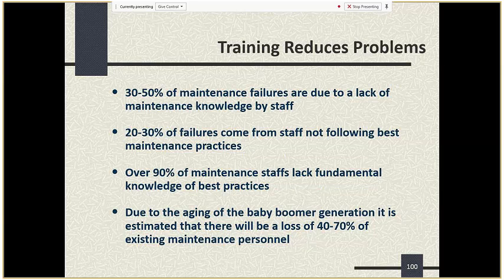Or sometimes, even if you know what to do, and you have the knowledge, maybe you just don't have enough time or budget, and you don't follow the best maintenance practice, and so there can be a failure with respect to some particular piece of equipment. Filter changing is a great example of that. I've seen many cases where filters were supposed to be being changed, and that was low on the totem pole of their maintenance path, so they didn't get changed. It created issues.